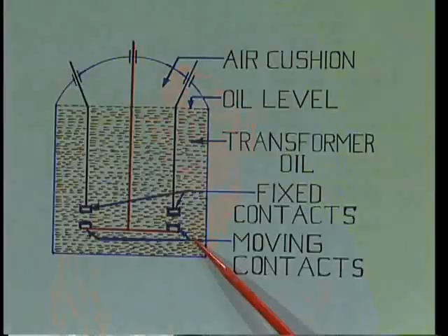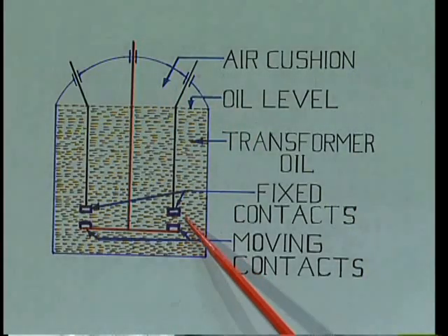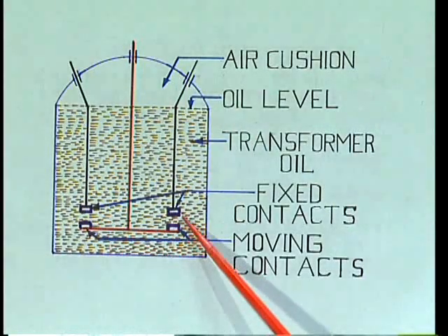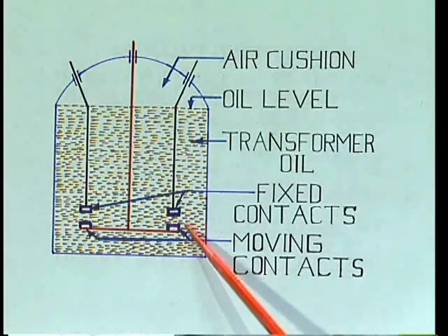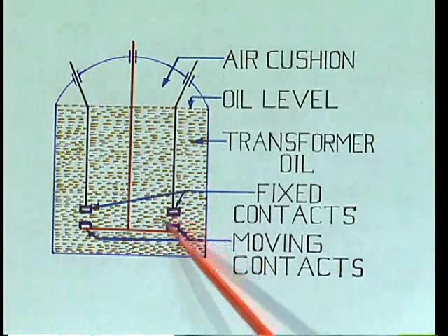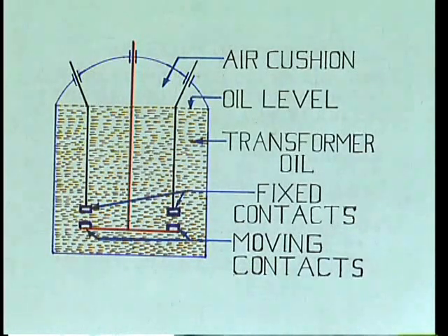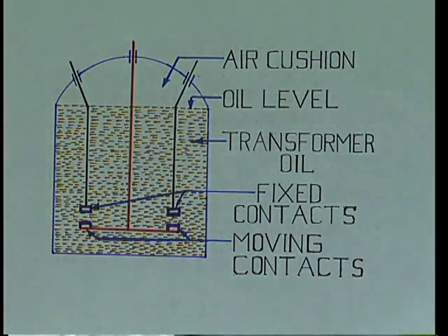So in this bulk oil circuit breaker, the arc is established across the breaker. The arc evaporates the surrounding oil into hydrogen gas, which has excellent cooling properties, so the arc can be extinguished as early as possible. Once a certain gap length is reached, the arc is extinguished. Therefore the current can be interrupted. Like this, plain tank oil circuit breakers work.